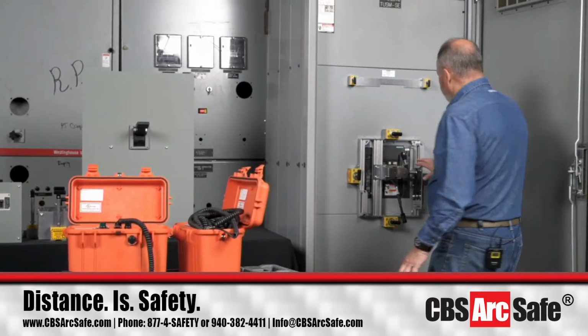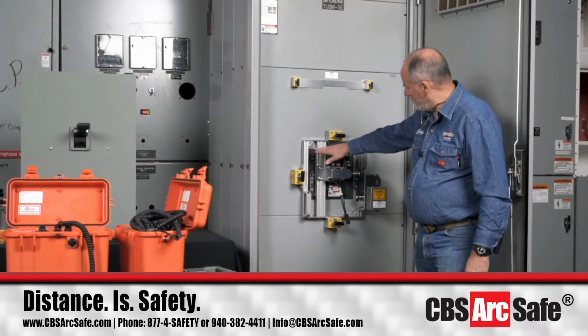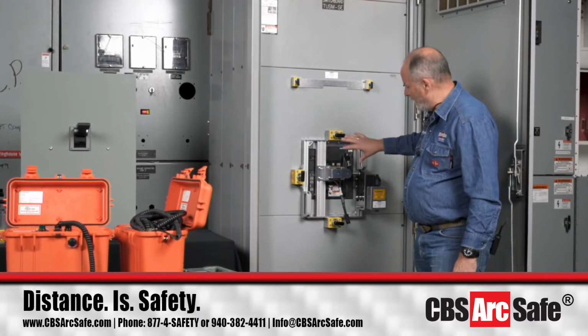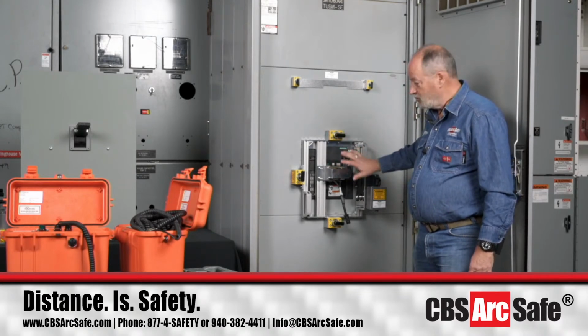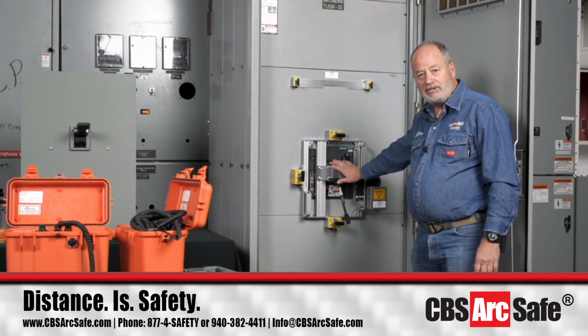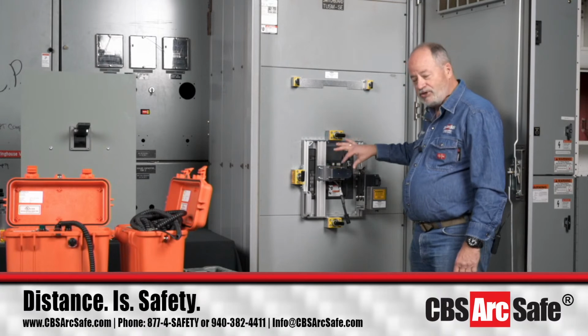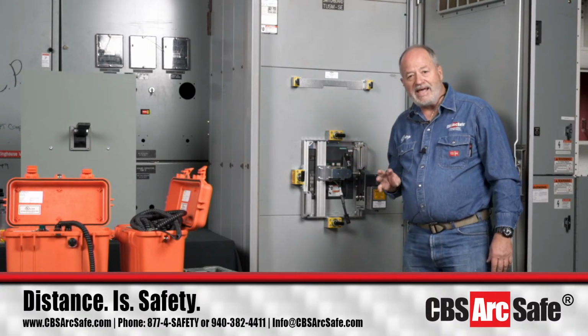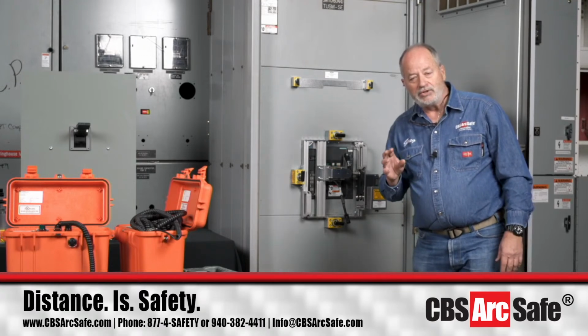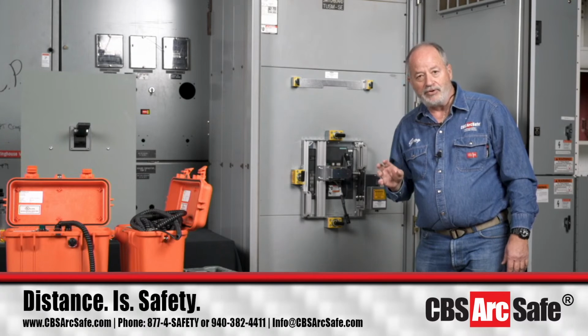This one itself that we've got here today is a fixed mount, and the way that this is all designed is to go around the face of the fixed mount when it's going to charge, close, and trip this breaker. So this one is set up specifically for what it's made for. This RSA can also accommodate the escutcheon, okay, as far as that goes, but we do need to have pictures of what you got so we can verify when we build it we're giving you the right application for your solution set.